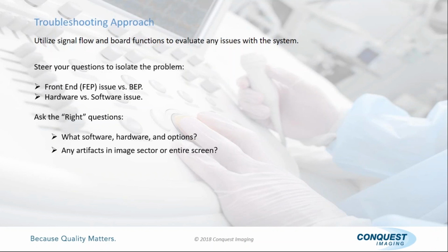So, artifact inside the image area, meaning if I was to go in here, is it inside the image area or is it all the way outside of the image area? Okay, that tells you. If it's outside the image area, it can't be a front end problem. Front end doesn't know anything about the rest of the area. It only knows the actual image area. Okay? Here, when you get up here, look, there's a pixel missing in this one.